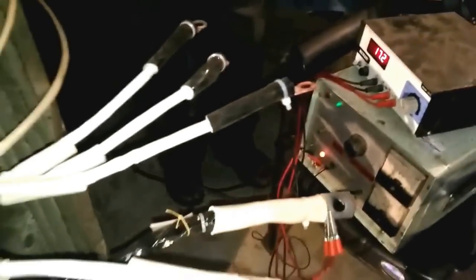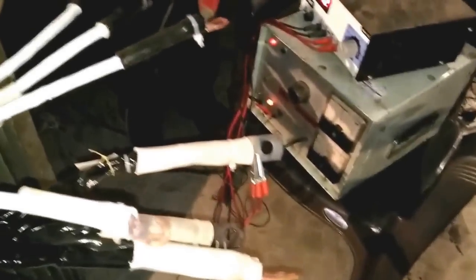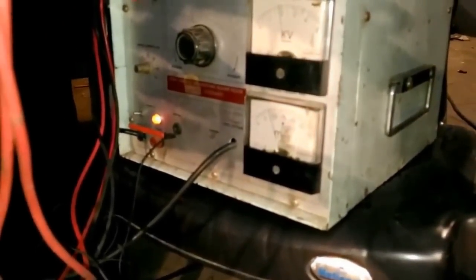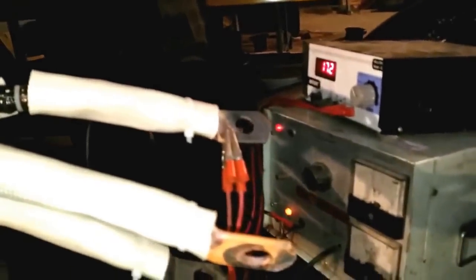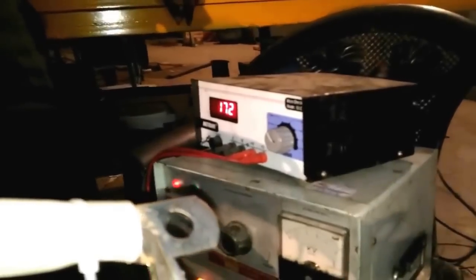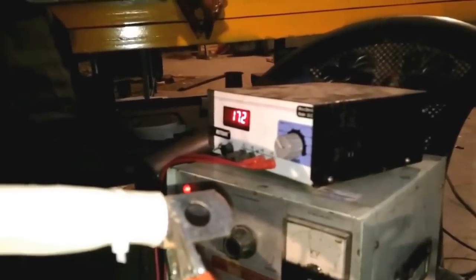So the windings are being flashed at 2 kilovolts. You can see we're flashing 2 kilovolts. It's got a leakage current of 8 milliamps. It's going to be flashed for 3 seconds. So in the same way we have done phase-to-phase testing also. And lower winding is going for a resistance testing. You can see 17.2. That's the resistance that we had.